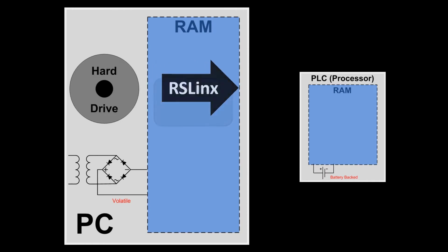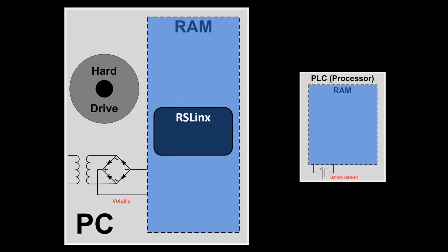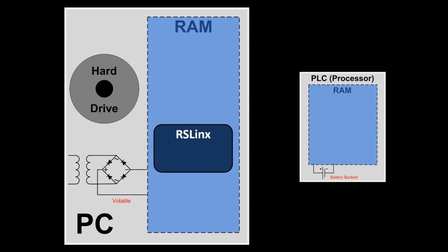So the first piece of software that you open is RSLinx. RSLinx is a driver manager for your COM ports. And your PLC will have COM ports and your computer will have COM ports. I show the PLC with two because that's very typical. If it were a ControlLogix, you have one port on the front and the back connector that plugs into the backplane is also a COM port. Most PLCs have two COM ports. The Micro 810 only has one COM port. So the Micro 810 is very deficient in capability. So typically we like to recommend the 820 and up.